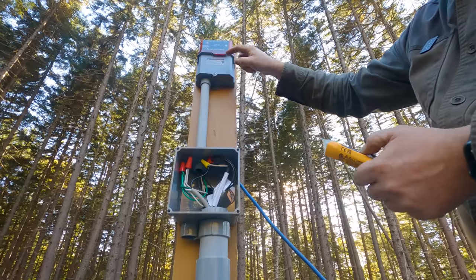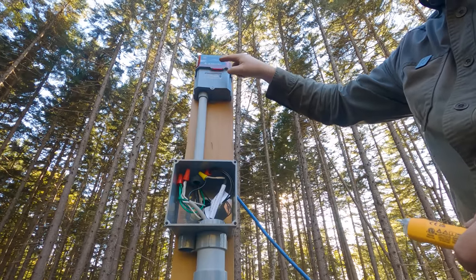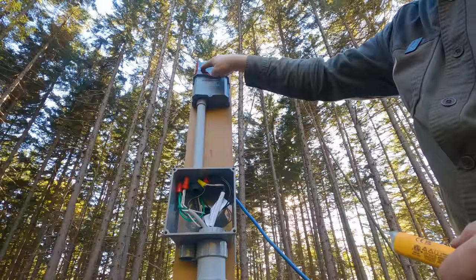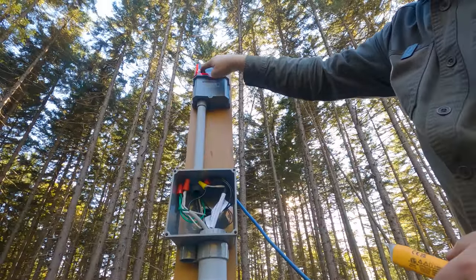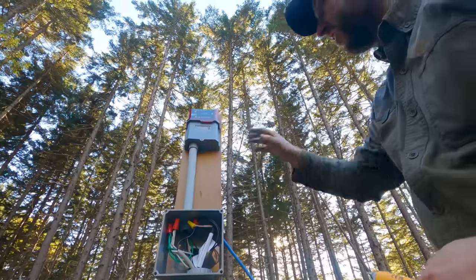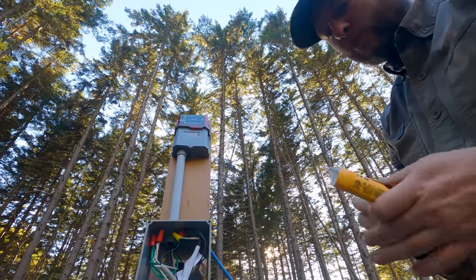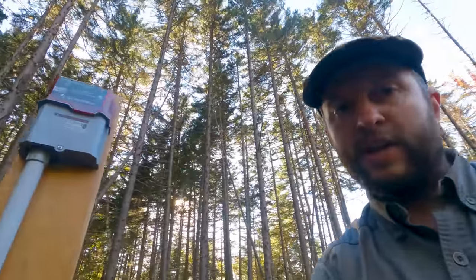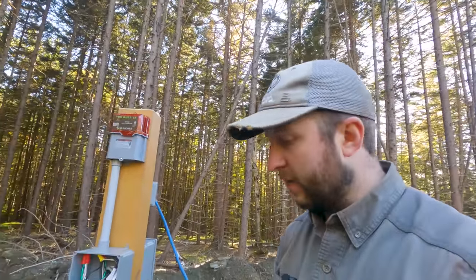Turn off my tester. This could be quite loud. I think there's a siren and a flashing light. So just bear with. So this lights up and that alarm goes off when the alarm triggers, and that is triggered by the float switch. So let's see if Diana can trigger the float switch and make that alarm sound.